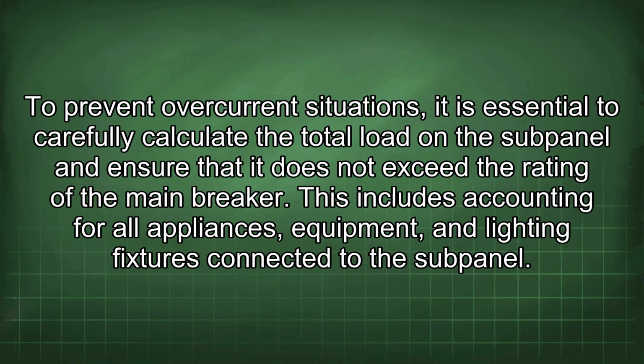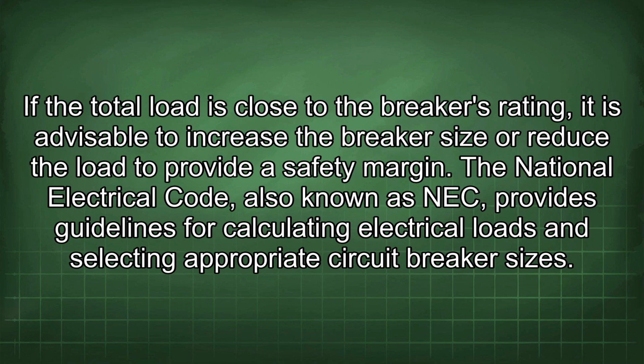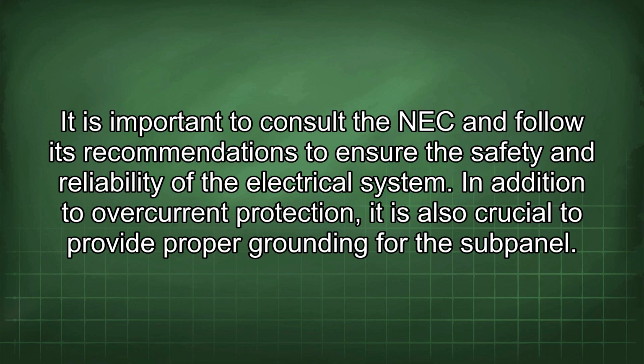To prevent overcurrent situations, it is essential to carefully calculate the total load on the subpanel and ensure that it does not exceed the rating of the main breaker. This includes accounting for all appliances, equipment, and lighting fixtures connected to the subpanel. If the total load is close to the breaker's rating, it is advisable to increase the breaker size or reduce the load to provide a safety margin. The National Electrical Code, also known as NEC, provides guidelines for calculating electrical loads and selecting appropriate circuit breaker sizes. It is important to consult the NEC and follow its recommendations to ensure the safety and reliability of the electrical system.